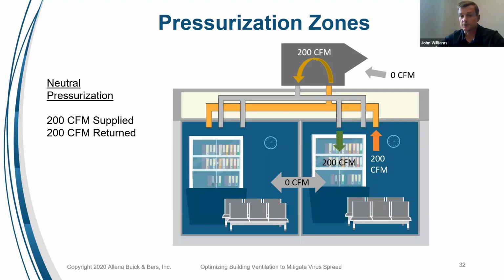Simple graphs, some simple little diagrams here. This is a room with a neutral pressurization. For illustration purposes, I'm sure some people will pick this up. The air volume shown in the air handler only represents the room on the right in our diagram. In this example, we have 200 CFM of air supplied to the room and 200 CFM of air is returned. So therefore, our room pressurization is neutral. There's no air movement from the room on the left to the room on the right.